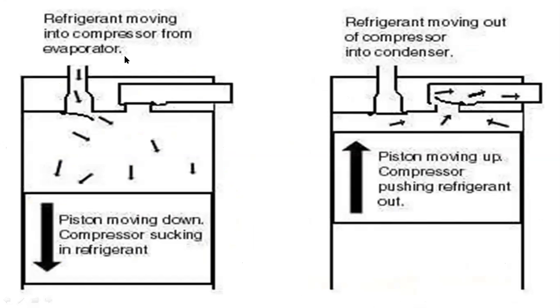In the case of a refrigeration compressor, refrigerant moves into the compressor from the evaporator. In a typical closed-loop refrigeration system, when the piston is going out it sucks refrigerant into the cylinder, and when it moves up it compresses the refrigerant, increasing the pressure and sending it through the discharge valve. During suction when the piston is going out, the discharge port is closed and the suction valve is open. During compression when the piston is going up, the suction is closed and the discharge valve is open.